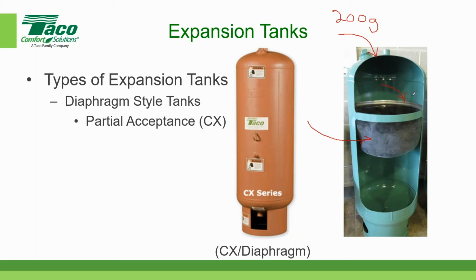One of the major differences between diaphragm style tanks and the other style tanks is that in certain models, the bladder can be replaced. So you can take the bladder out if it should fail for some reason and replace it. In a diaphragm style tank, it's not only partial acceptance, but the diaphragm cannot be replaced. If it should fail for some reason, you cannot repair the tank. We can't fix it. You have to dispose of the tank and purchase a new one. So those are the different style tanks.